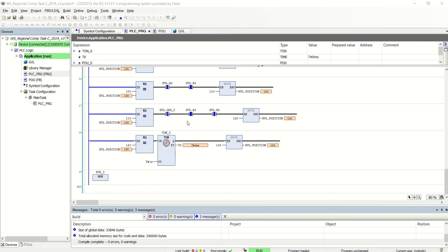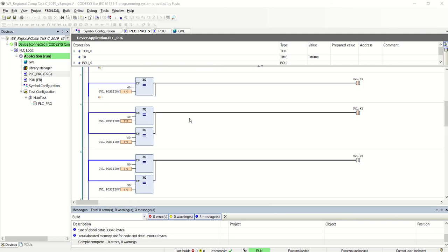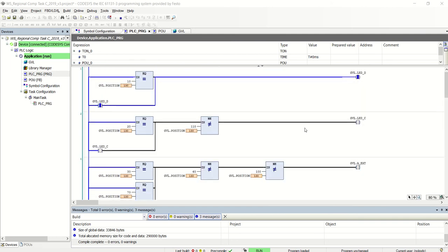Yeah, I did just check back, and it does time. It's just only a second, so it happens pretty quickly. But like I said, you could use those step numbers to see where it broke down, and check whether you have the right inputs triggering, or the right step numbers triggering the right outputs in those scenarios. So that's one way of testing it.